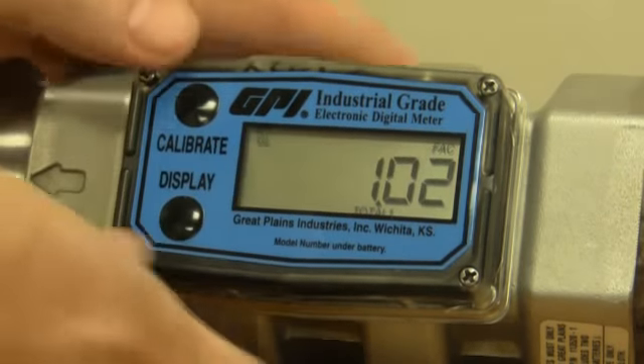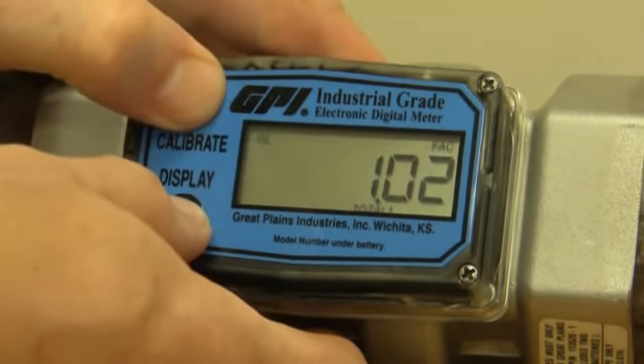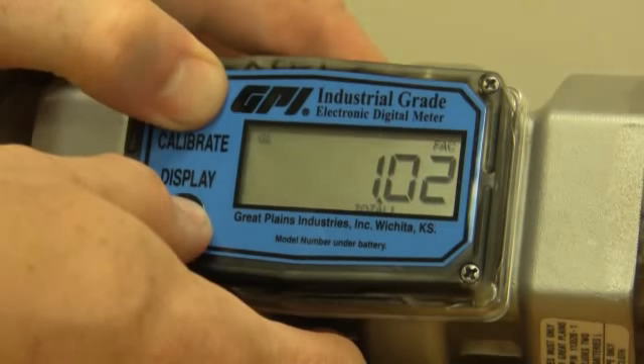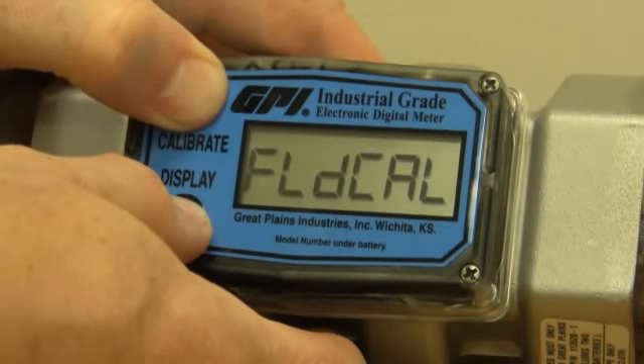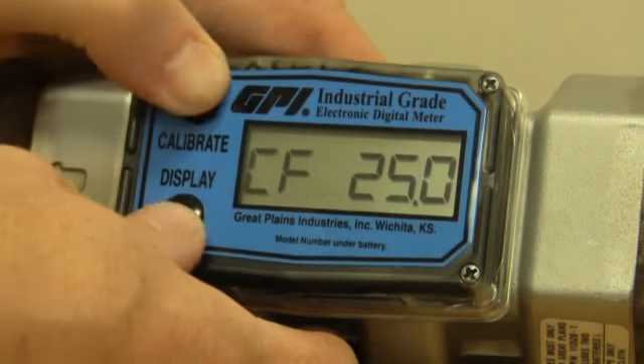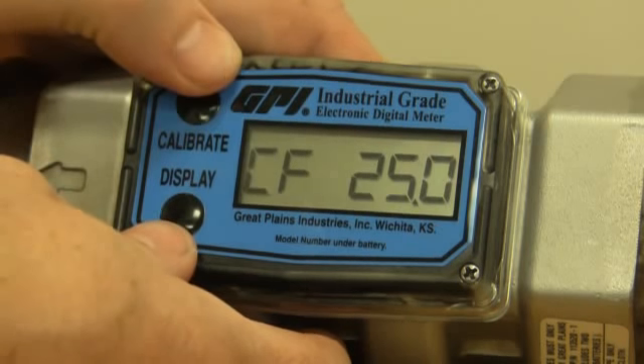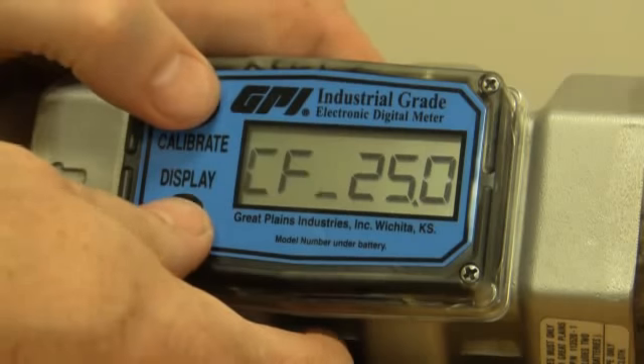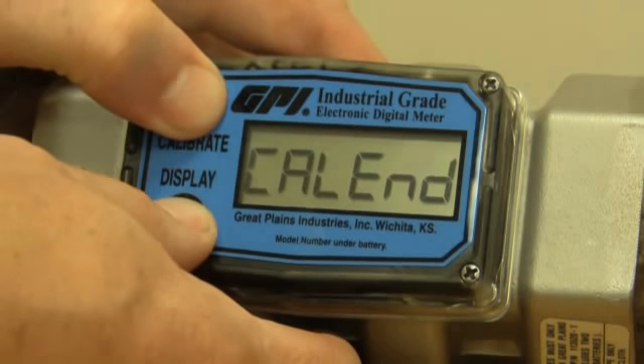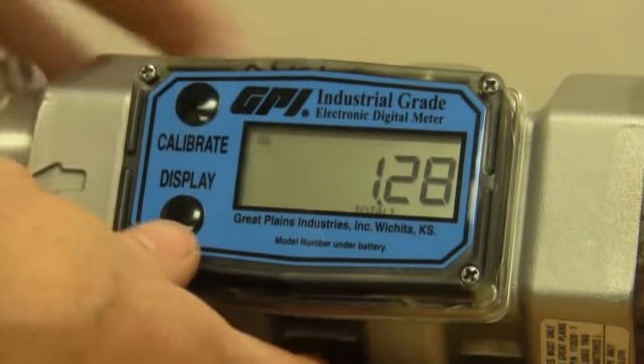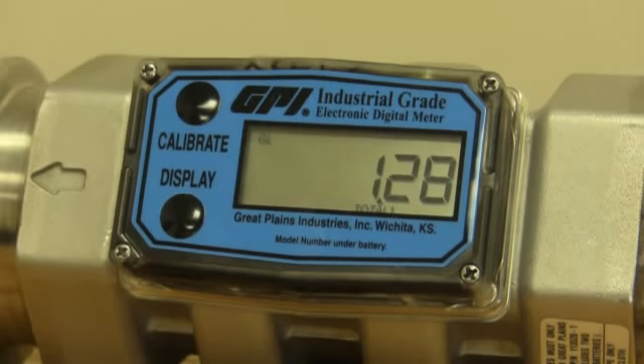Now, of course, you may be somebody that switches back and forth between water and the thicker fluid like antifreeze. So if you want to go back, again, you just hold down both buttons, wait, and it says field cal. Going back to that field calibration, and it still has the last number we put in there. Still got the 25. So we're just going to go ahead and hold down both buttons again. It says end cal, and we're back into the field calibration.